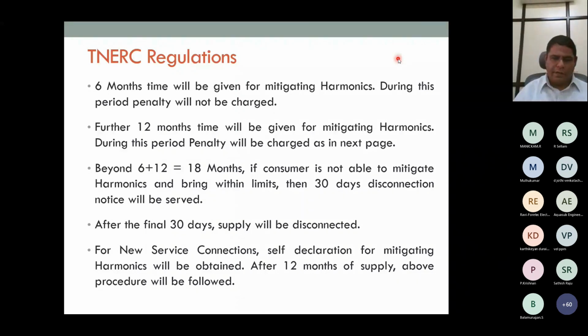Penalty is not a flat 15%. Last time it was a flat 15%. Even if you went 0.1% in excess, like 8.1 or 8.2, they gave a flat 15% penalty, and it was a very cumbersome process. People were put into a lot of difficulties. So totally, right now there will be 18 months time, and even after 18 months a 30 days disconnection notice will be given. That is only in rare cases where people are not able to bring within limits. But 18 months is a fairly normal time with which people will be able to mitigate, is what we believe from our side. So how much is the penalty? This is the penalty table.